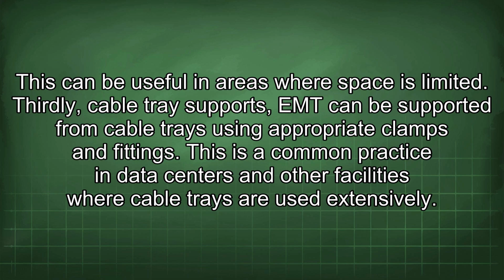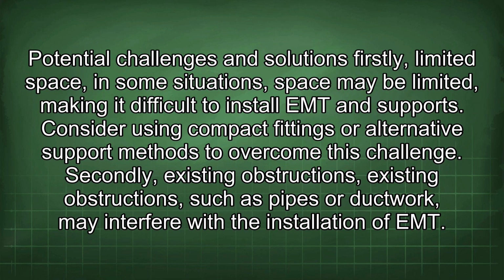Thirdly, cable tray supports. EMT can be supported from cable trays using appropriate clamps and fittings. This is a common practice in data centers and other facilities where cable trays are used extensively. Potential challenges and solutions. Firstly, limited space. In some situations, space may be limited, making it difficult to install EMT and supports. Consider using compact fittings or alternative support methods to overcome this challenge.